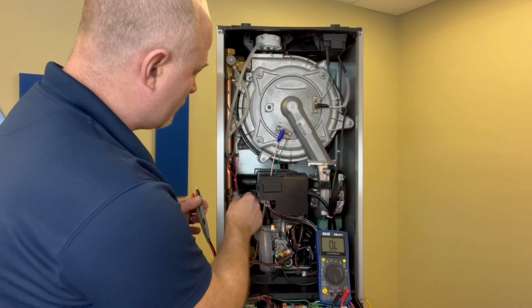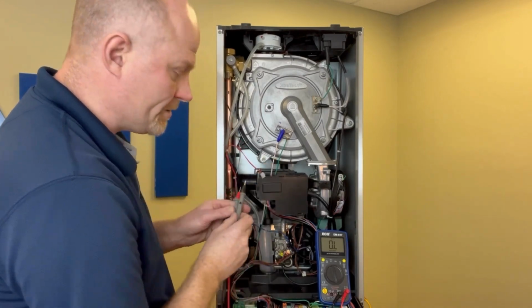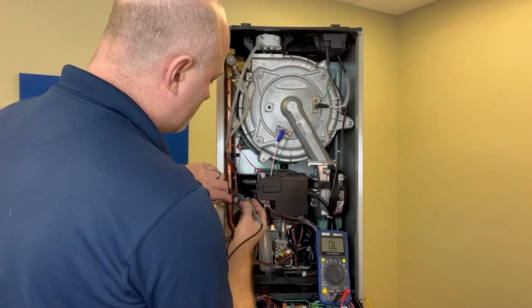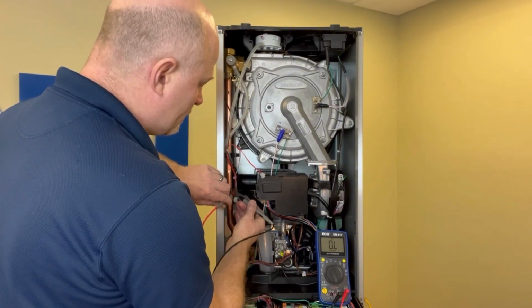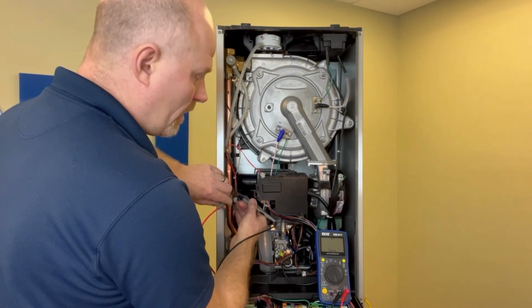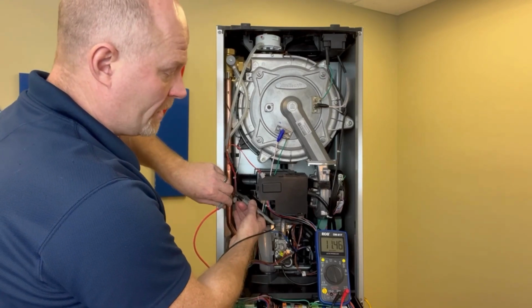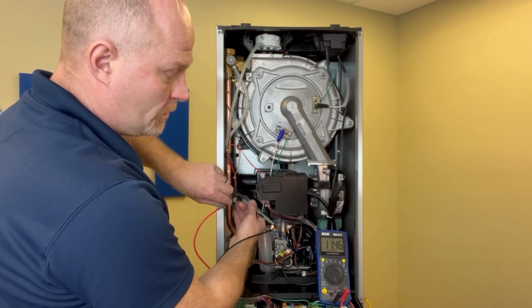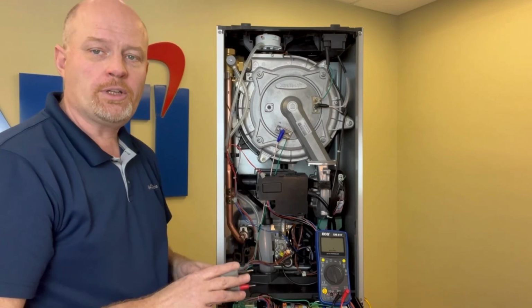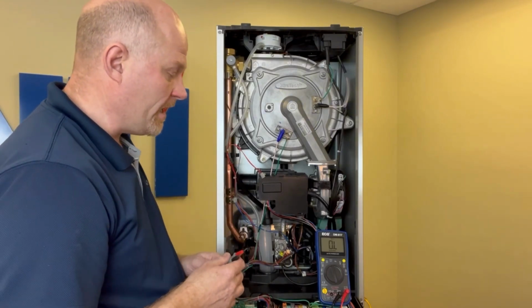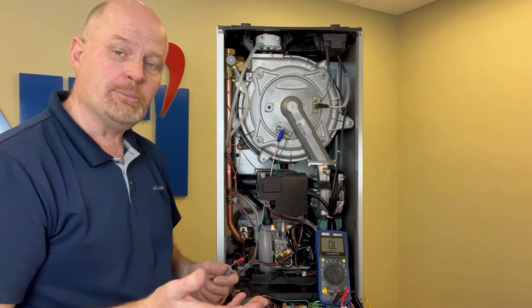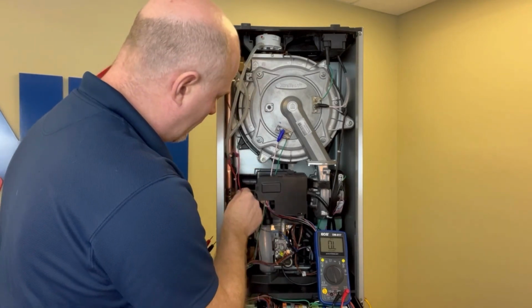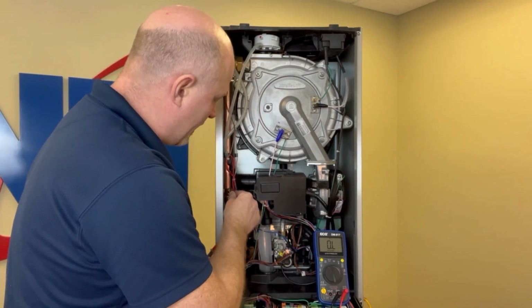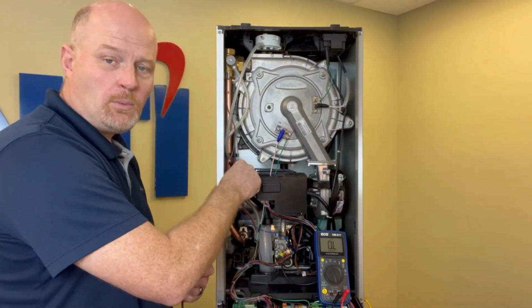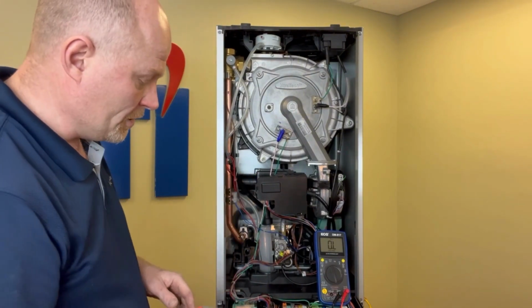What we're going to do first, I'm going to disconnect the sensor, take my two meter probes, and touch one leg each of the sensor. When I do that, I get a reading of 11.46 kilo ohms, which is about right. We're a little bit colder than 77 degrees Fahrenheit in this room, and we should get a reading a little bit higher than 10,000 ohms. I'm going to plug that sensor back in, and that was the supply sensor, the red wires. The next thing I'm going to do is move down to the circuit board.